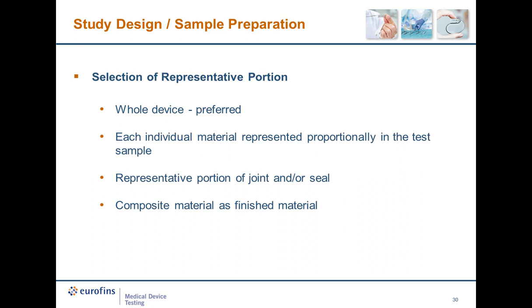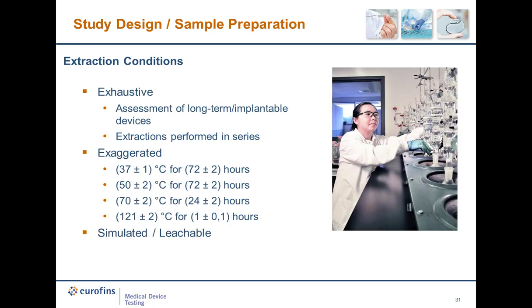First, a sponsor will need to determine if the entire device can be evaluated. The standard does state that the use of the whole device is preferred. However, there are situations in which it is not possible to evaluate the entire device. If a decision is made to evaluate components of the device separately, the standard recommends evaluating the materials proportionally in the test sample. If there are joints or seals, those need to be included in the evaluation, since these areas tend to be a higher risk for potential leachables. Another key point to make is the material should be tested as they would be used, meaning if the device is sterilized before use, it should be sterilized as part of the sample preparation.